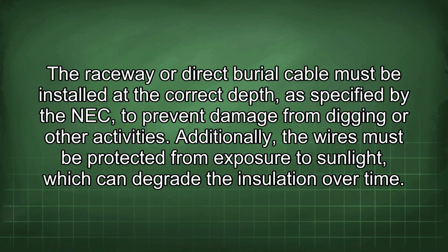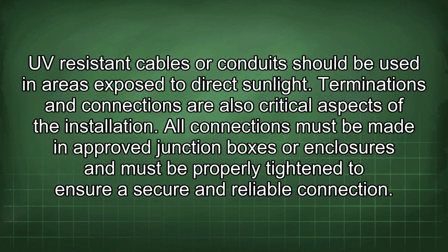Additionally, the wires must be protected from exposure to sunlight, which can degrade the insulation over time. UV-resistant cables or conduits should be used in areas exposed to direct sunlight. Terminations and connections are also critical aspects of the installation.